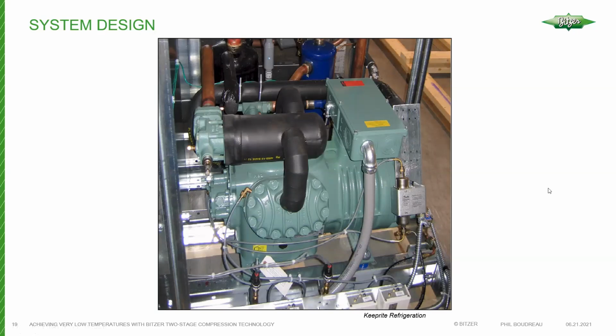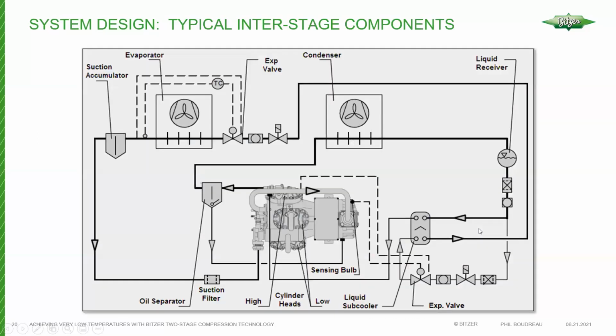So let's take a look at some system design of the two-stage. Okay, so here's the most common way to apply a two-stage compressor in, say, a condensing unit. We have the interstage, which I mentioned before, and the main components needed in a subcooling type approach. We have interstage cooling. That's a requirement, no matter what, with a two-stage compressor. But since we have access to an interstage, this gives us the ability to set up another evaporator, if you will, and use that evaporator to cool the refrigerant that leaves the receiver and travels towards the expansion valve on the main low temp evaporator.